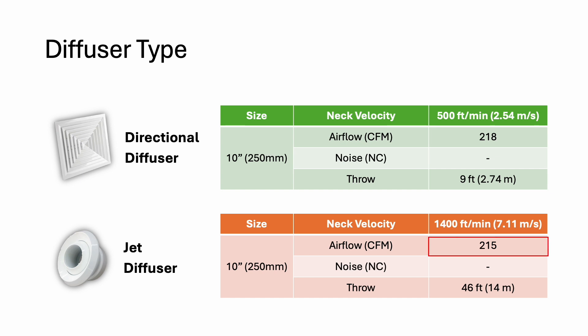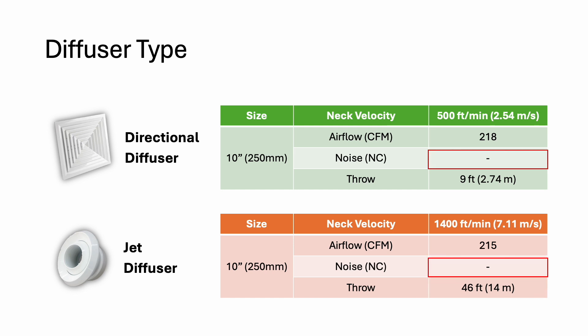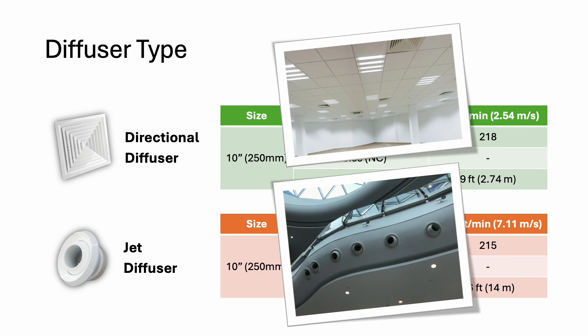For the same airflow, a 10-inch jet diffuser has a throw distance as far as 46 feet. Despite that, both diffusers produce negligible noise. So comparing these two, a directional diffuser is more suitable for home and office use because the ceiling height in these places is typically 9 to 10 feet only. Whereas a jet diffuser is more suitable in places where people are very far away from the diffuser — for example, airports and the famous Qatar World Cup stadium.